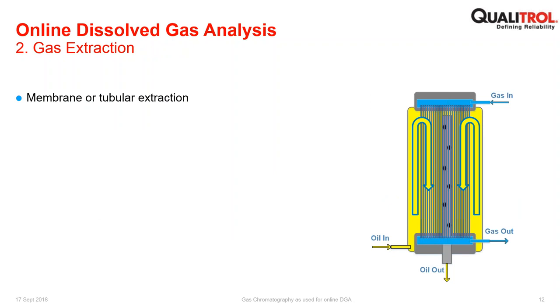For gas extraction, there are a number of methods that I've already mentioned. The one used in the Qualitrol device is membrane or tubular extraction. So gas permeable tubes isolate oil flow from extracted gas volume, and it's illustrated here, oil in yellow and gas phase in blue. And essentially there is no mixing of the oil into the gas phase. So what you have is an isolated gas phase and an isolated oil phase. The gas can move through the walls of the tubes that form part of this membrane extraction system.